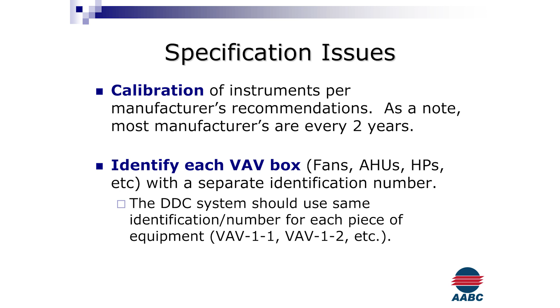Specification issues. First is calibration of instruments. A lot of manufacturers mandate that you get your manometers, hydronic or air, calibrated every 2 years. Personally, we've got 25 guys out in the field, and I do every single one of their air and water meters every year. I don't want to fall back on that 2-year mark and find out 18 months in that one of my meters was way out of whack, because then I'm thinking I need to go back and figure out where that meter was and whether I need to do some QA/QC on it. So I just accept it and send my stuff out every year as a practice. I think a lot of the AABC firms you'll come across are doing the same thing.